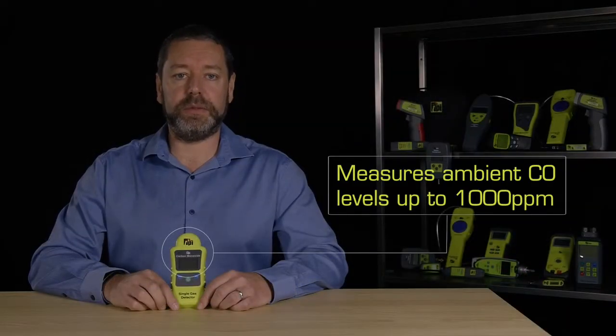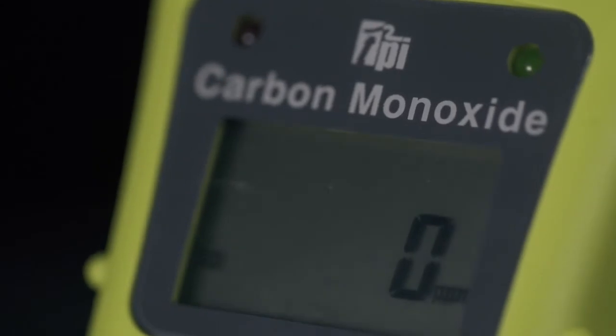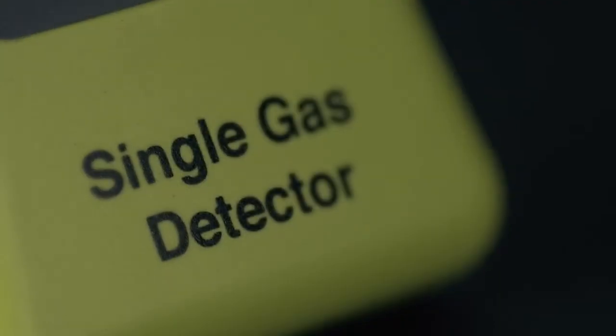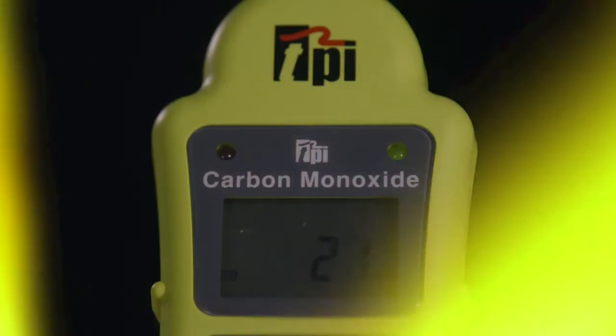This instrument will measure ambient CO levels up to 1000 ppm and will measure and record the peak value of CO since it was last switched off, with an alarm level set at 30 ppm.